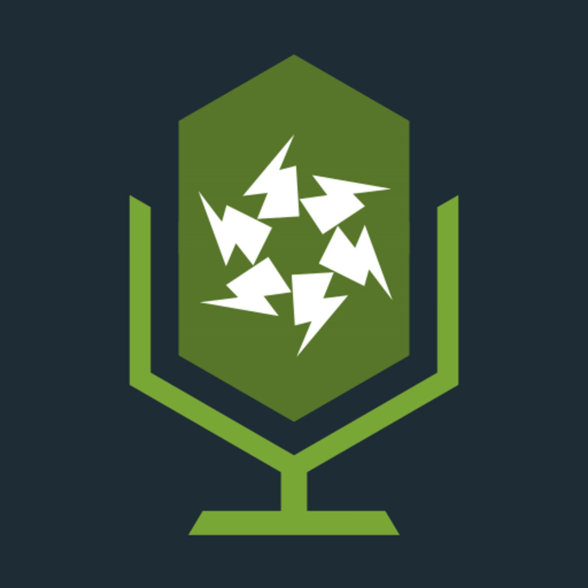Some more examples of RCDs for other than additional protection, which we just touched on really. 500 milliamp is used in construction sites for 32 amps. We have 300 milliamp here for fire protection purposes. In agriculture, horticulture, we have 300, 100, and 30. So they're very fond of RCDs in agricultural installations.